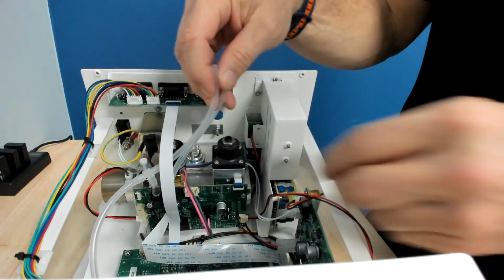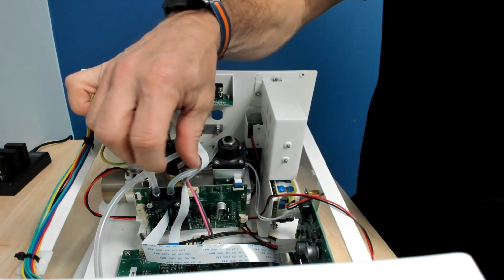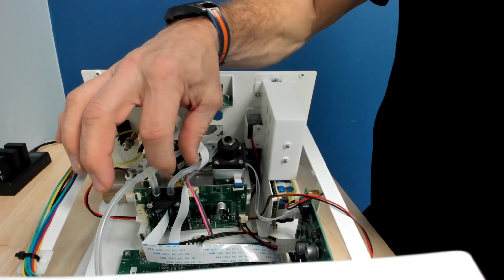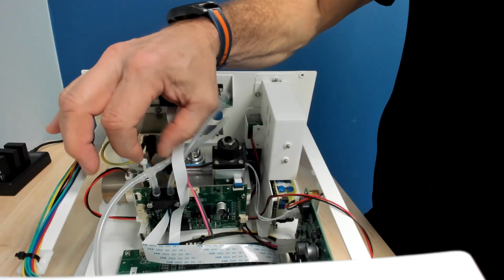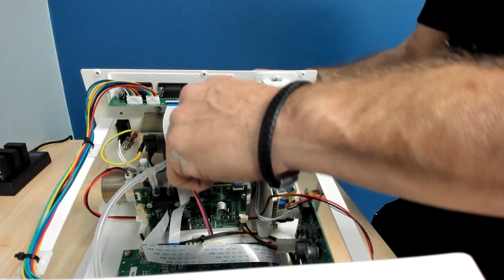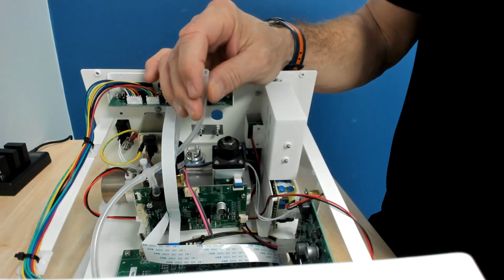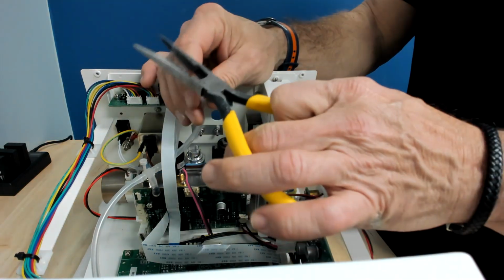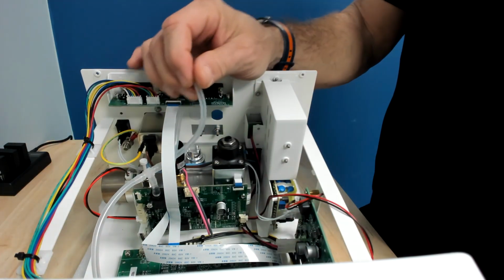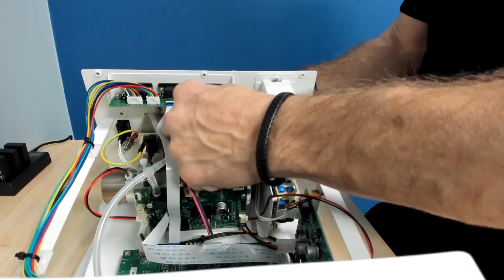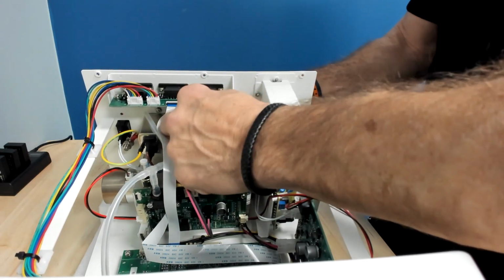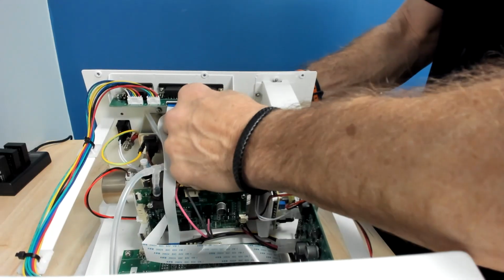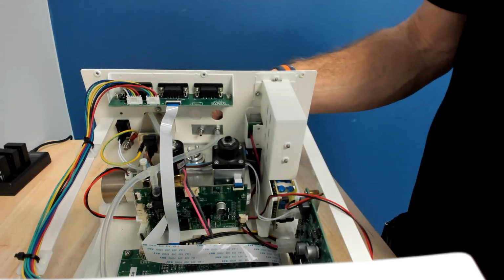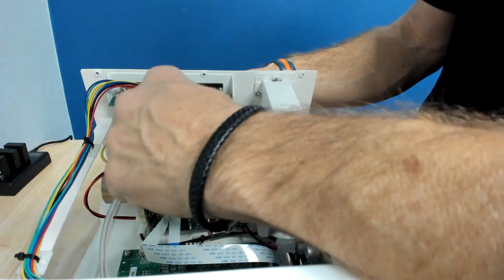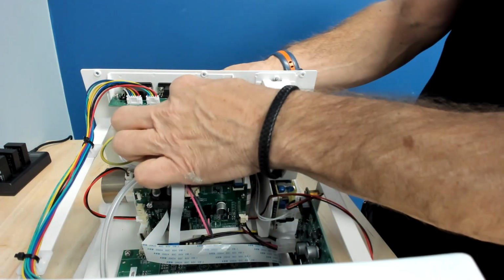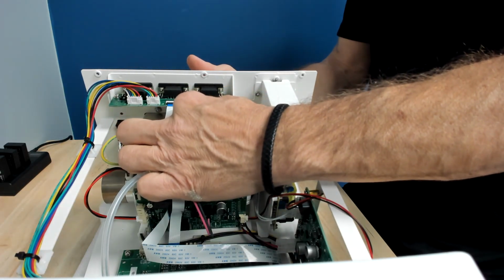Now, the longer, so if you're coming off this, this is our transducer that gives us our pressure and also our spirometry. So the teed one goes to the far side, and that would be the clear inlet if you were looking at the outside. I'm just going to clean the edge of that hose up, insert it, and make sure I get that hose the whole way over the nipple. And then go ahead and take our short one here, and that goes to what would be the equivalent on the blue tubing on the outlet.